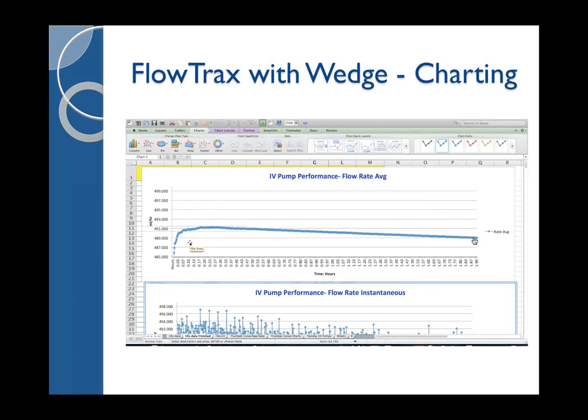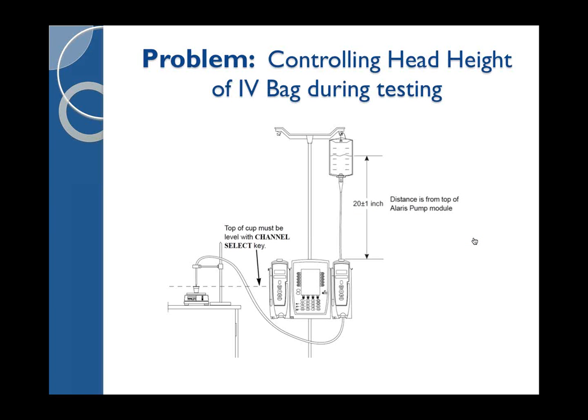this characteristic of infusion pumps is actually tied, in part, to the head height requirements that manufacturers have. So here's an example of a test procedure page from an IV pump manufacturer showing what they require you to do when you're testing the IV pump. They want you to have the fluid height, not the IV bag, but the actual fluid height, to be 20 inches above the pump, plus or minus 1 inch, which is really difficult to maintain if you're testing 50 or 60 pumps in a day's time, because you'd have to pour fluid into the IV bag every 5 minutes to meet that requirement.